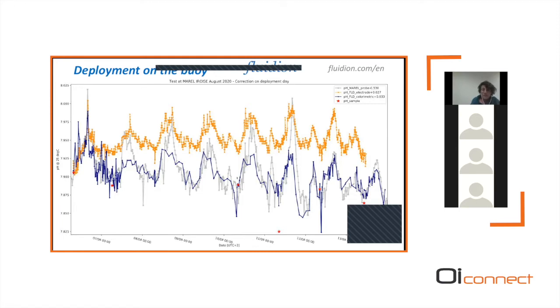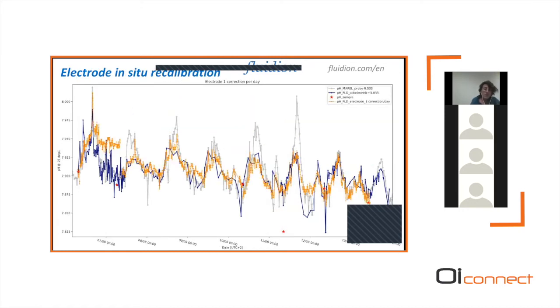Also, all the sensors show this diurnal pattern. But one thing is that the electrode is not showing the decreasing trend. So there is a drift, as was mentioned before, that happens with the potentiometric sensors from this electrode. So then we looked at how to correct for this drift using the in situ calibration with the colorimetric analyzer. The first approach was very simple: use just one data point every day from the colorimetric analyzer and apply an offset on the rest of the electrode data.